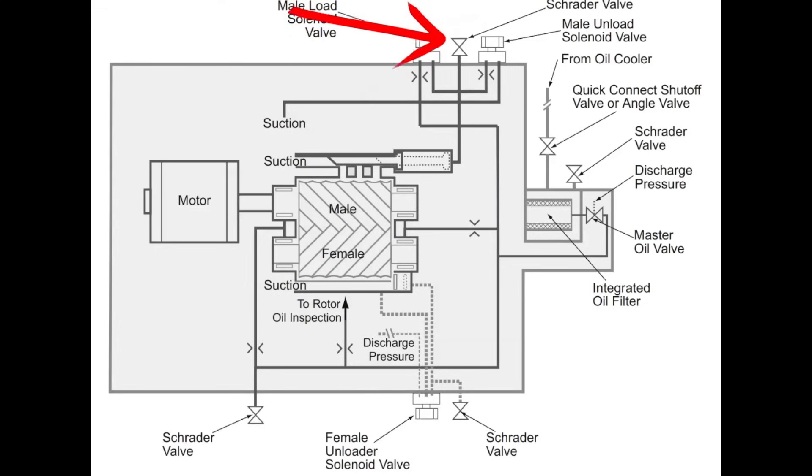So these are your male load and unload. These are controlling a slide valve which is internal to the compressor. And the female unloader is controlling a bypass. It's not a slide valve, it is an internal bypass. And they serve very different functions for the compressor.